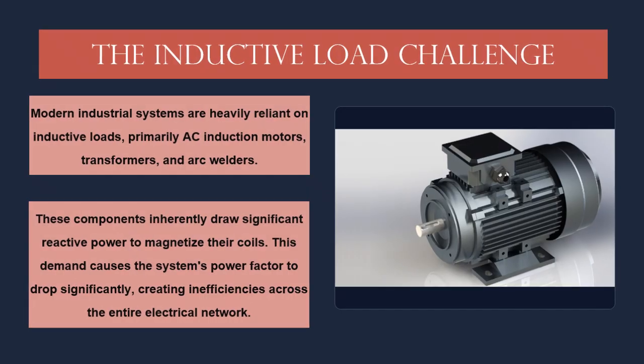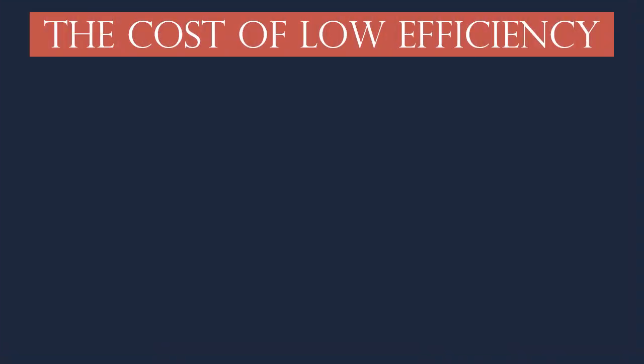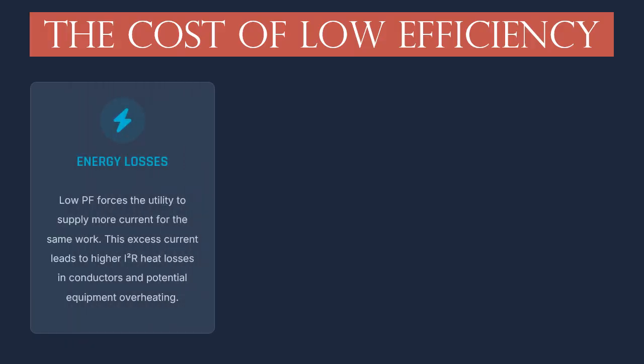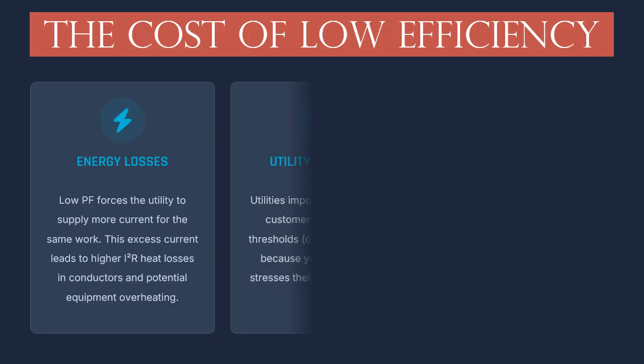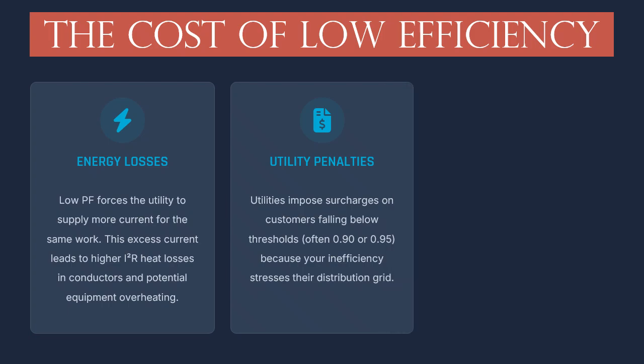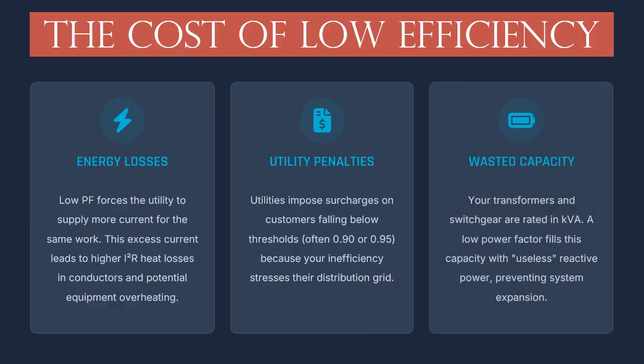The cost of low efficiency. Why does this matter? Because low efficiency has real-world consequences. First, there are energy losses. Drawing excess current generates heat, which damages insulation. Second, there are direct financial penalties. Utilities often surcharge you for stressing their grid. And third, you are wasting capacity, filling up your transformers with useless, reactive power instead of leaving room for expansion.